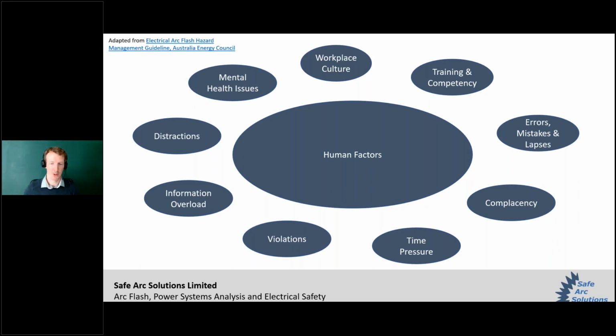Of course, what we have to recognize is that the biggest influence on arc flash is human factors. People make mistakes, fail to recognize the hazard, and fail to take appropriate precautions. These happenings are much more difficult to prevent without a more proactive approach to arc flash, centered around giving people knowledge and carrying out risk assessment. In a lot of cases you might have an arc resistant switchboard, but sometimes you have to defeat some of those protections in order to do the work you need to do. So it's better to have both an arc flash strategy as well, potentially, as using arc rated equipment, if that's the best way to look at it.